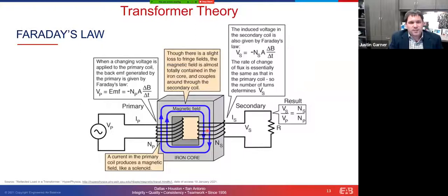I don't want to go too far down in the weeds, but if you open up one of these transformers, and I probably should have put a picture in here of that, but I didn't, you have different settings on those transformers for the secondary side. They're called tap settings. And so you can essentially step the voltage up or down, or the electrician can, excuse me, to get the right voltage based upon what's happening on the primary side. So you may have a utility that's feeding in a very high voltage, and you may have a secondary that doesn't have a lot of load on it, so you may need to step that down a little bit, or vice versa. That's something that the electrician has to look at, and we sometimes look at it on the commissioning side as well, to get the appropriate secondary voltage on the downstream side of these transformers.